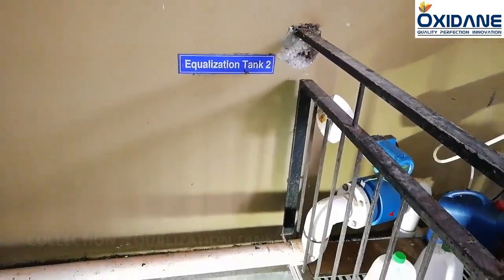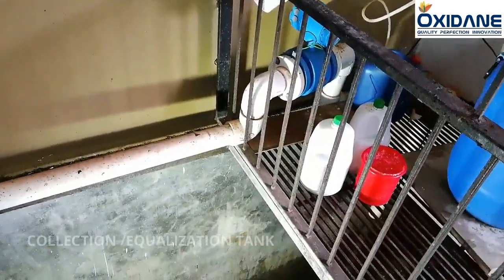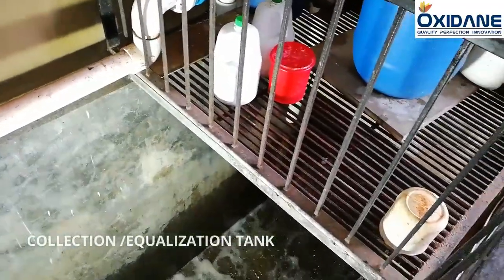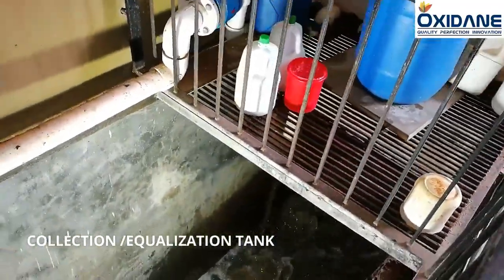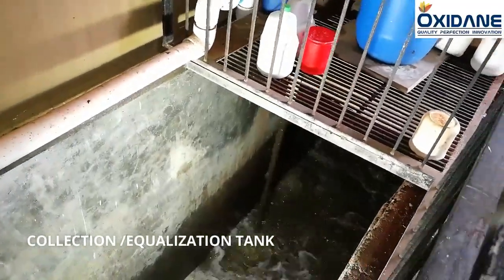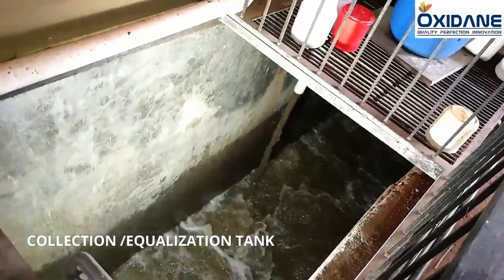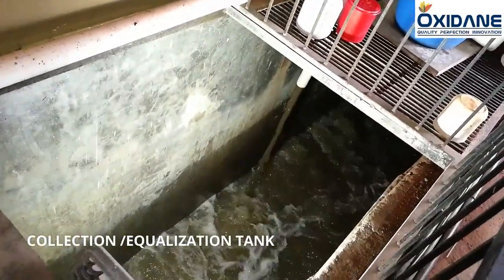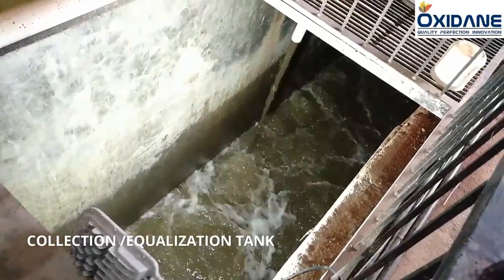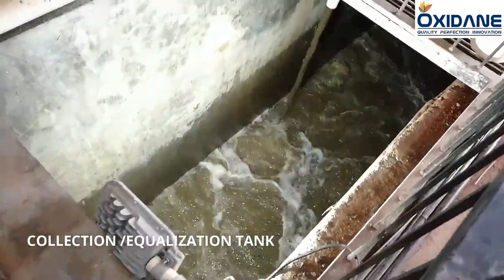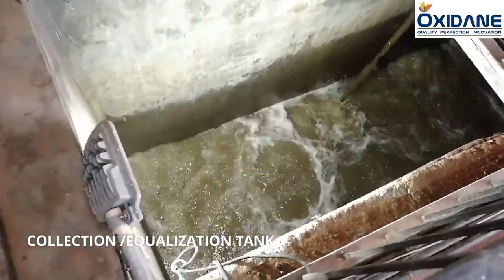Equalization tank. From the bar screen chamber, sewage comes to the equalization tank. The equalization tank is the first collection tank in an STP. Its main function is to act as a buffer, to collect the incoming raw sewage that comes at widely fluctuating rates, and pass it on to the rest of the STP at a steady flow rate.